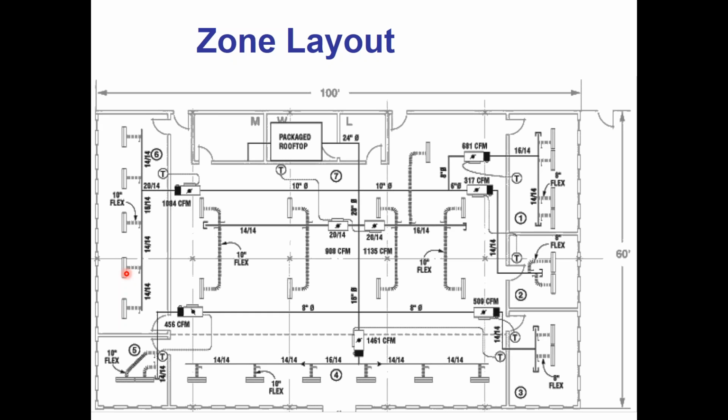It obviously would be not good from a first cost standpoint because now I got to buy 5 sets of controls instead of buying only 1 set of control for that area of the building. So what ends up happening, even if these are divided offices, in practice, is these zones often get combined. Someone will say, you know what, we're not doing that. We're not buying 5 of those. We got to get things under budget in this project.